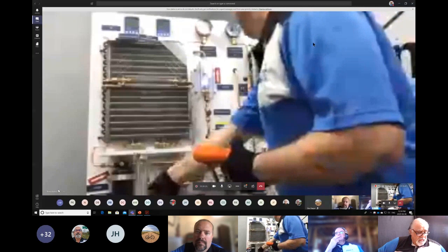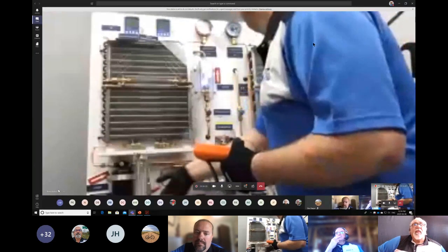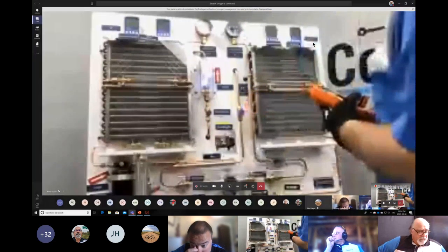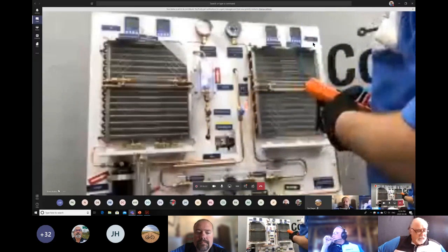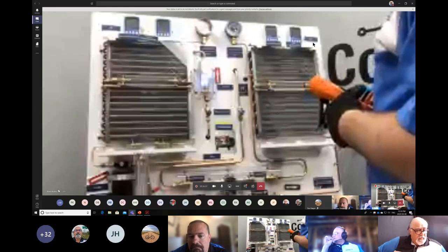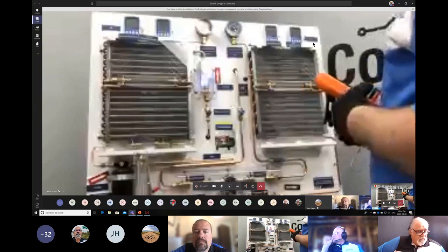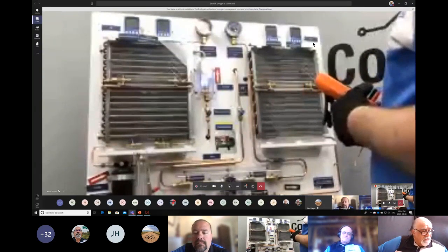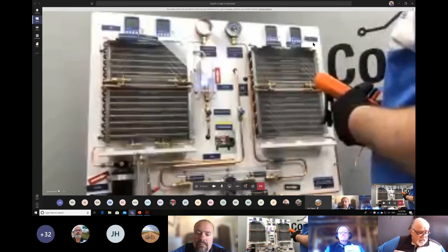Maybe I created too much of a restriction here. Yeah. Okay. Just a little bit. So I opened it up a little bit more. So I'm at around 25 pressure. Okay. So 25 psi is 24 degrees.